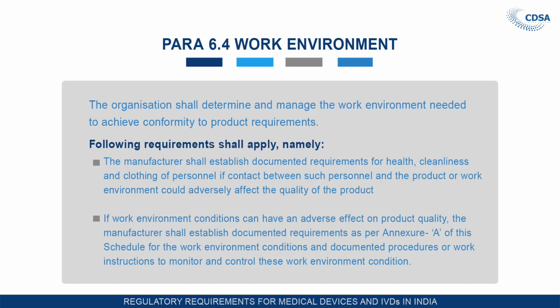Work environment. The organization shall determine and manage the work environment needed to achieve conformity to product requirement. Following requirements shall apply, namely, the manufacturer shall establish documented requirement for health, cleanliness and clothing of personnel, if contact between such personnel and the product or work environment could adversely affect the quality of the product. This actually means that whether the product requires that the personnel should change over to clean uniforms, wear gloves before touching the products, change their shoes and things like that. And if not, why it's not required.